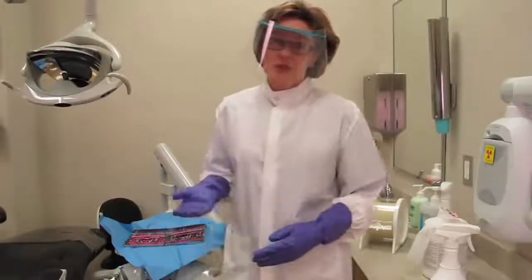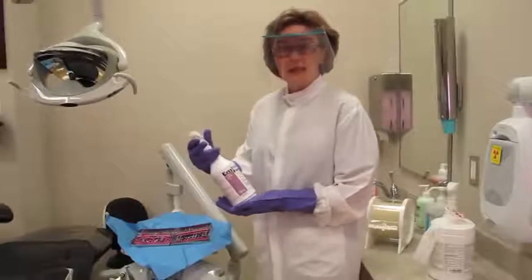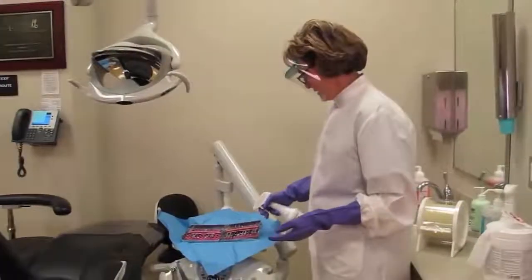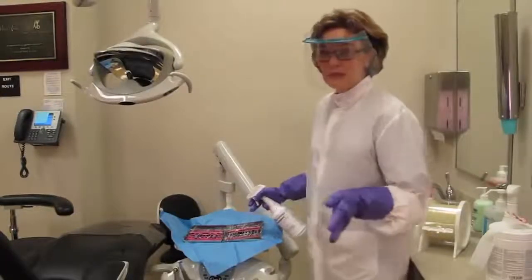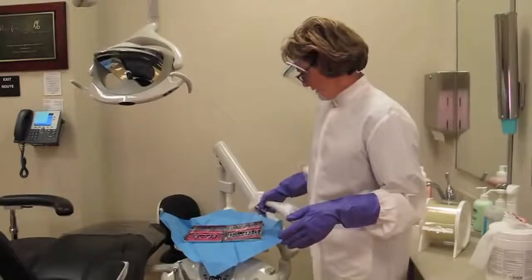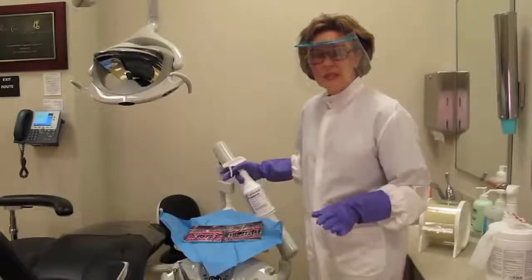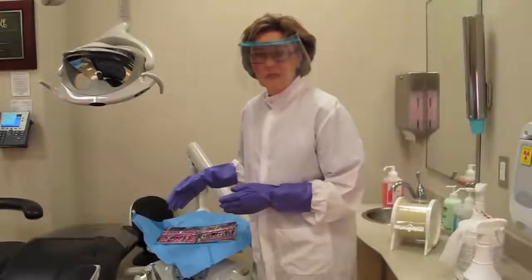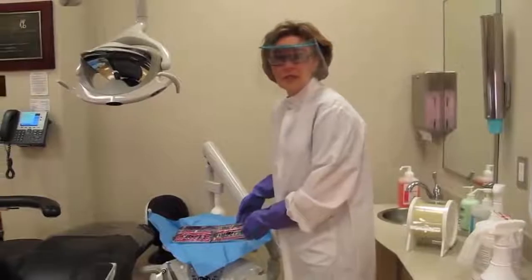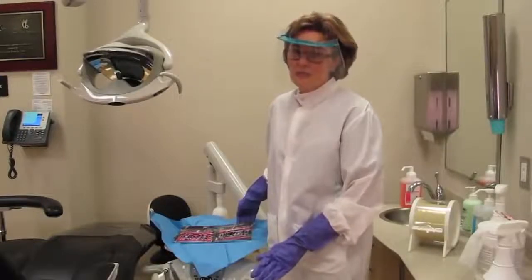So if you want to streamline the process, a great way of doing it is to basically use an enzymatic foam that sprays on your instrument and starts the cleaning process right there while you're tearing down the unit. So you just spray everything, let it sit, and it's like a holding solution, and it takes the place of a soak, and the enzyme starts breaking down proteinaceous materials. So these instruments can stay for 5, 10, 15 minutes, 30 minutes, however long it takes you to get to them in your busy day.